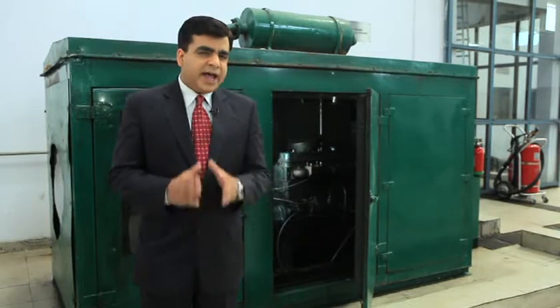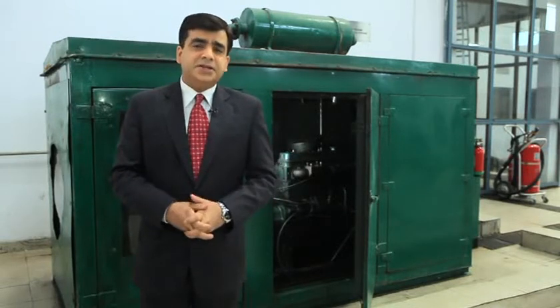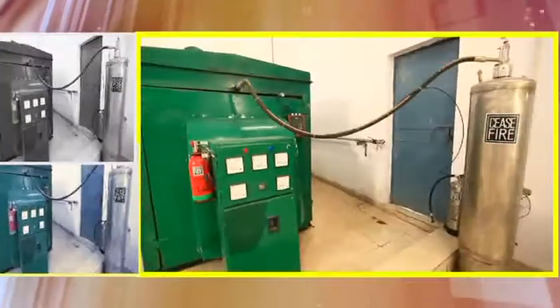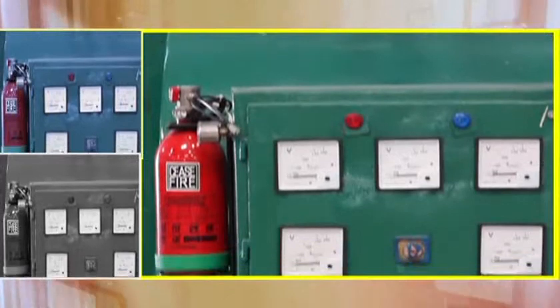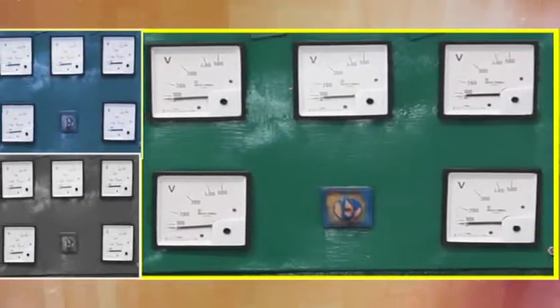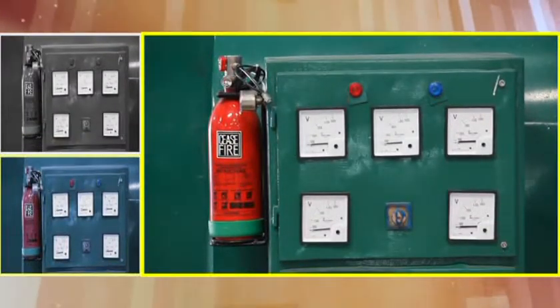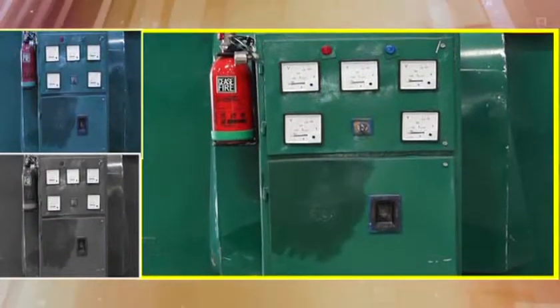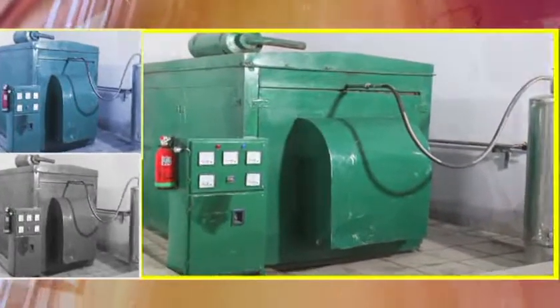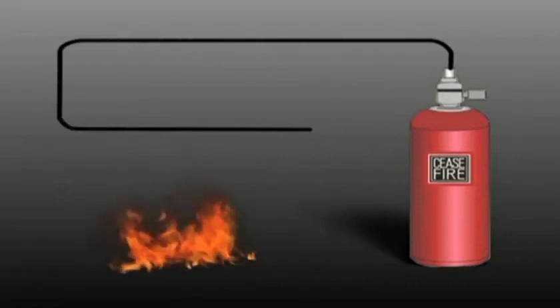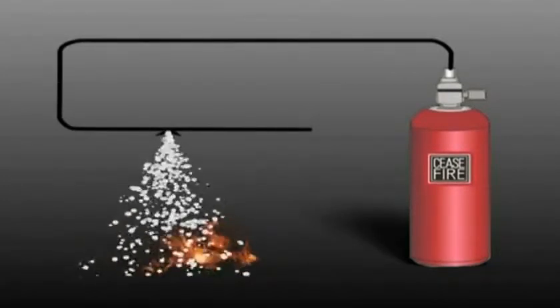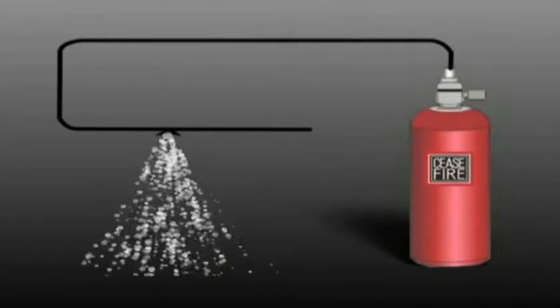But the Ceasefire Generator Auto-Quell System has another component to it as well, one that makes it especially effective. The generator control panel, which is especially high risk due to the presence of electricity, is protected by this system too. Heat sensing pneumatic tubes are laid around the fire risk area in the control panel microenvironment. They're designed to rupture and create a miniature nozzle with intense heat, discharging FE36 and flooding the microenvironment. This interferes with the fire's chemical reaction and prevents it from burning. Being a clean agent, FE36 leaves no residue, which makes it completely safe for electrical equipment.